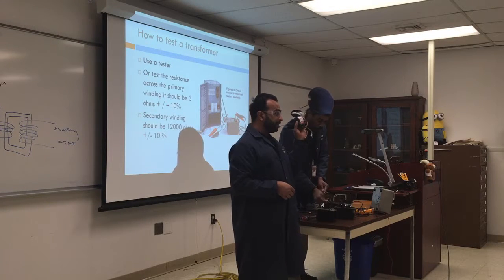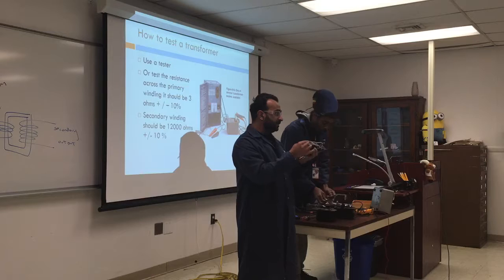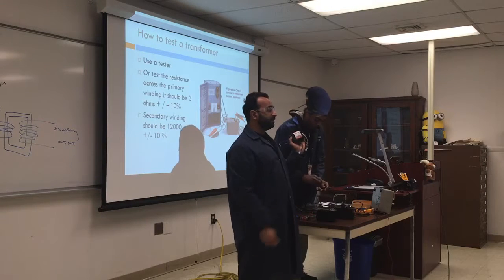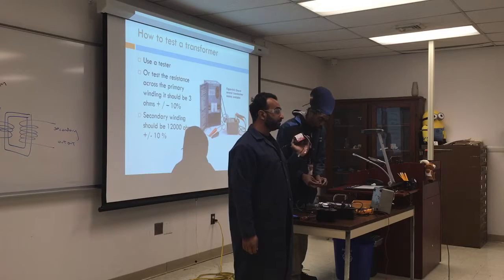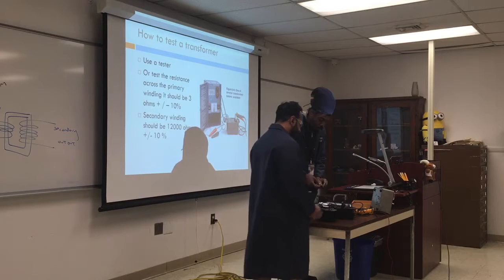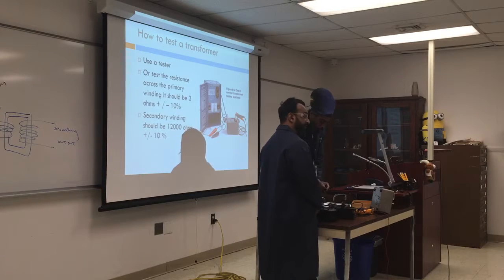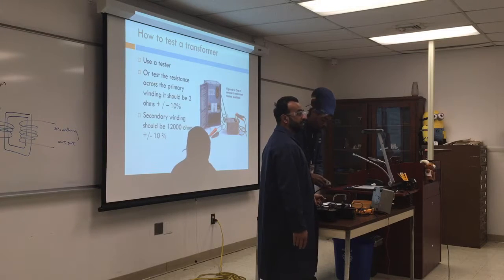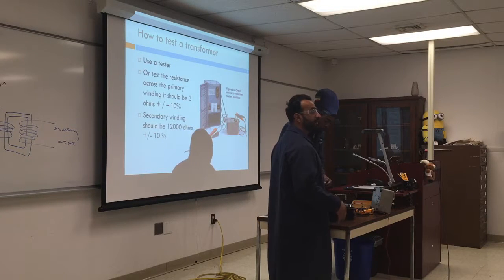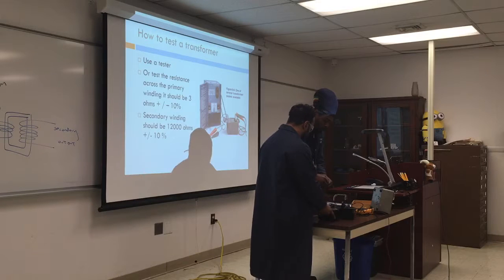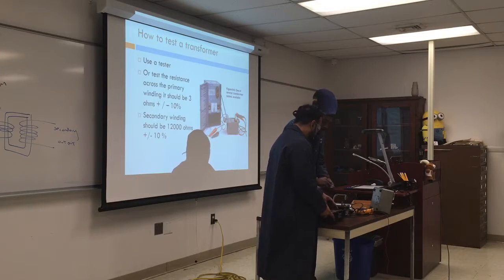Never, if you have an electronic transformer, test it by touching the leads together. You will burn it. So how do you test the electronic transformer? We don't. Either it works or it doesn't. If it doesn't work, replace it. It's not going to give you a weak spark. It's going to give you the right spark or a bad one.